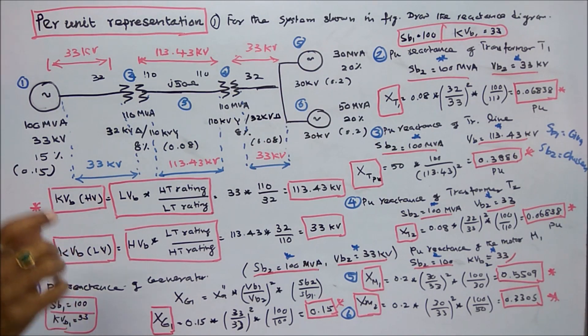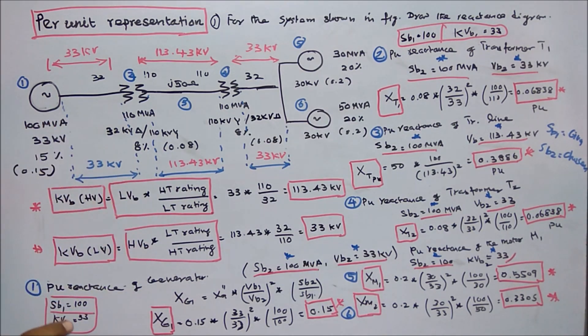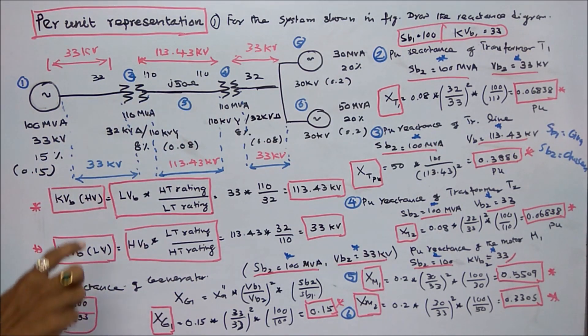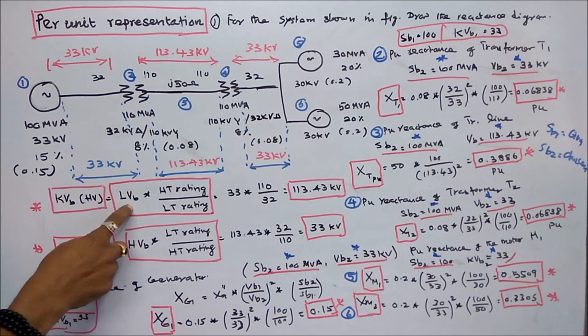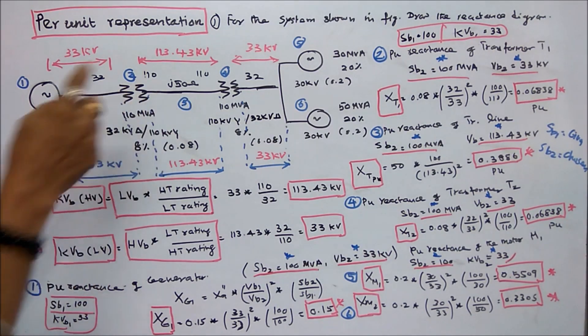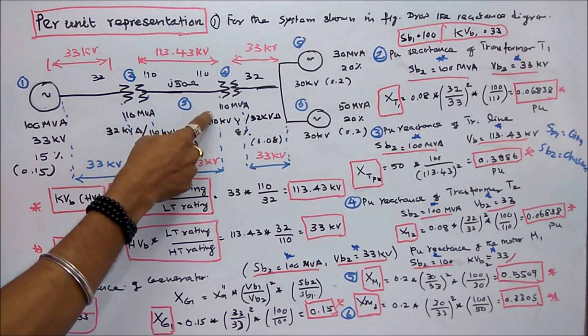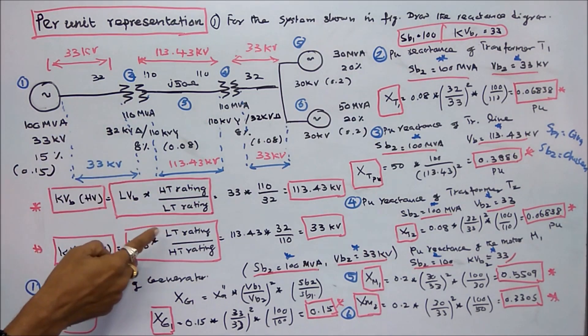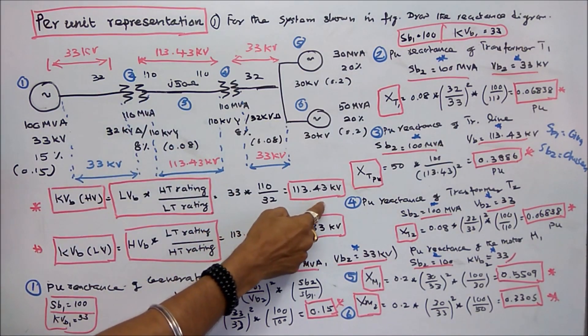We have to choose a base MVA and base kV. Base MVA is equal to 100. Base kV is equal to 33. We have to find what is the transmission voltage. High voltage kV base is equal to low voltage base of 33 kV into HT rating of 110, divided by LT rating of 32. That is 33 into 110 divided by 32, which equals 113.43 kV. This is the base kV of the transmission line.